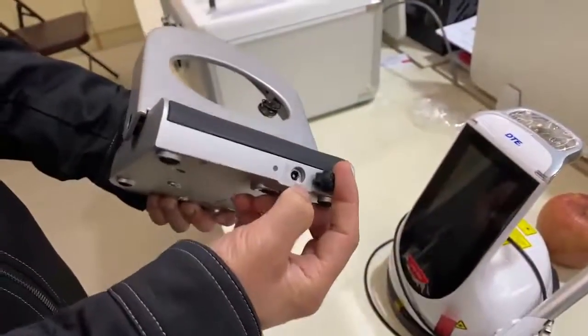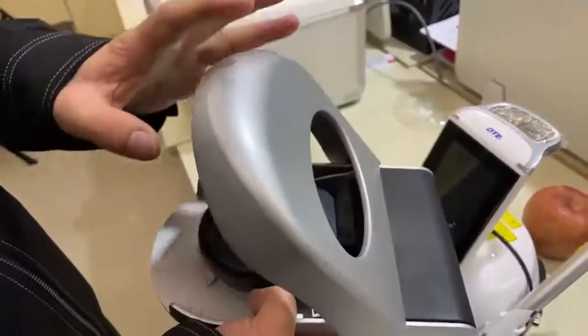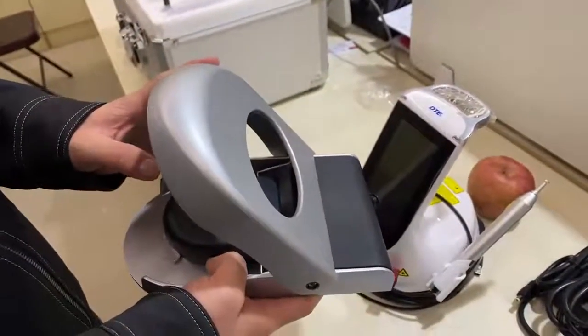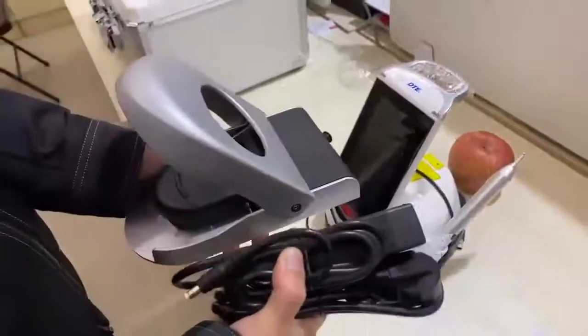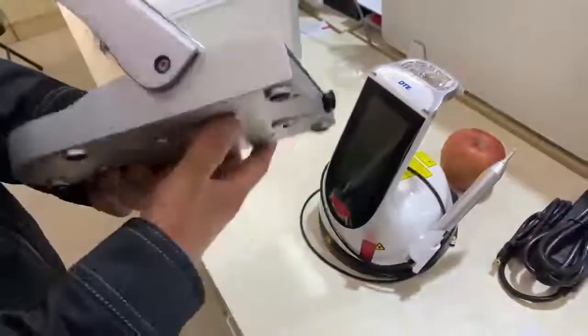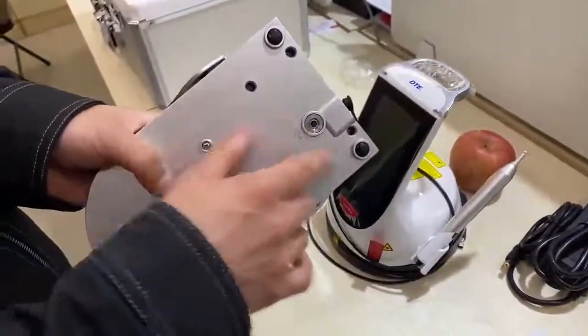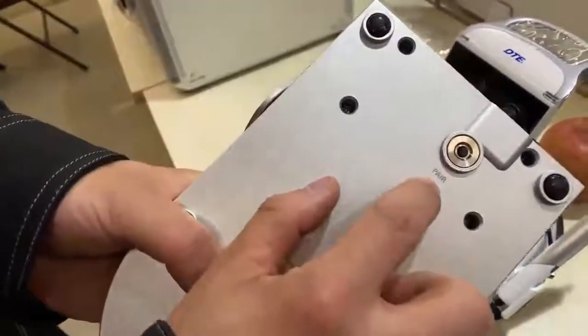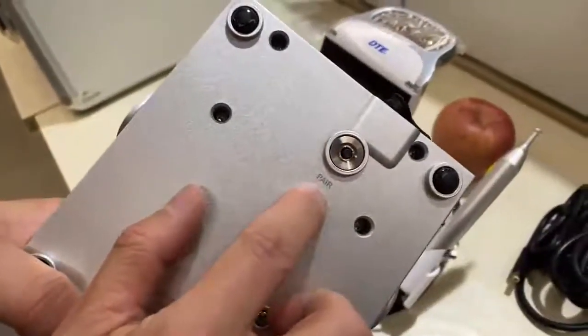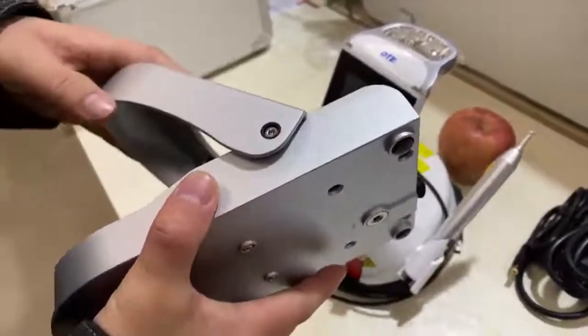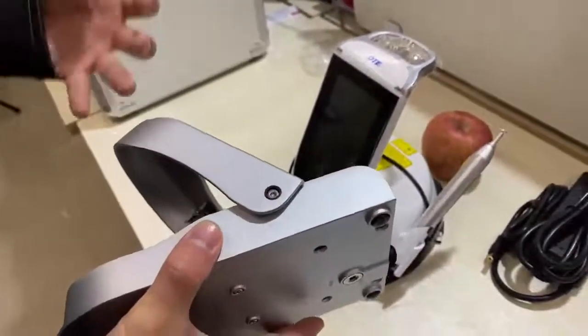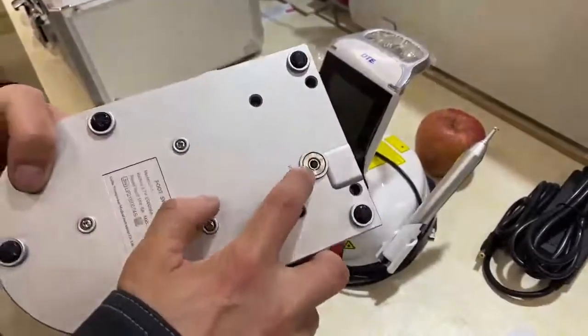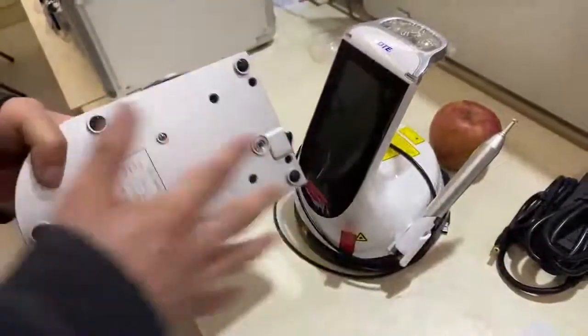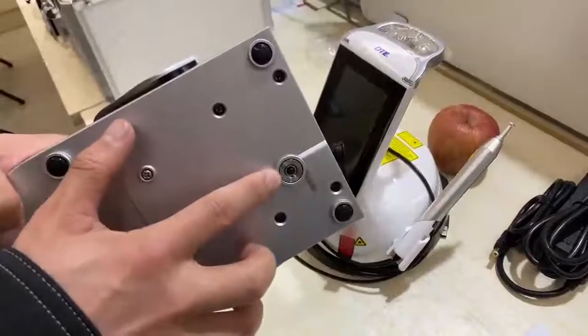And also you can see this is how we charge the foot pedal. Usually this foot pedal can be used for about 1 month after charging. And we can use the same power supply to charge the foot pedal. At the bottom of the foot pedal, you can see we have a pair button here. Sometimes if the foot pedal cannot work, or if you have got a new foot pedal, you have to press the pair button to match the foot pedal with the device. So this is the pair button. Okay.